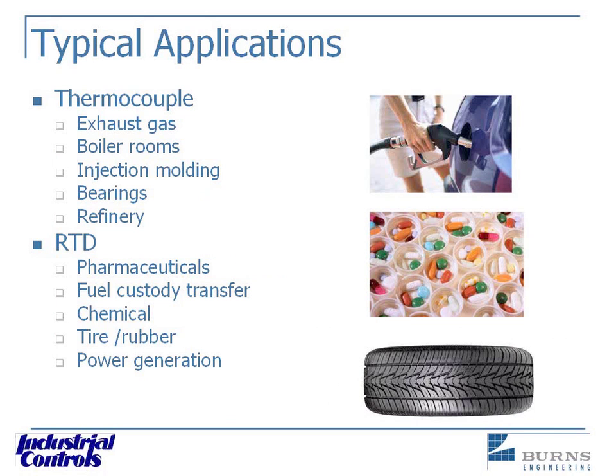And places where temperature is really critical and accuracy is of the utmost importance, pharmaceuticals. Huge place in the area for RTD usage. Fuel custody transfer, where oil companies are transferring gasoline, for example, that might be in an underground storage tank, and they're pumping it into a rail car that's sitting out in the sun, and it's 110 degrees. They need to know the very quick and accurate temperature of that fuel as it's coming out of the ground going into that tanker car, so that they don't overfill the tanker car. That fuel is going to expand as it gets hot, and it can be very easy to actually be not only overfilling the tanker, but not charging the correct amount for what they're putting in there.